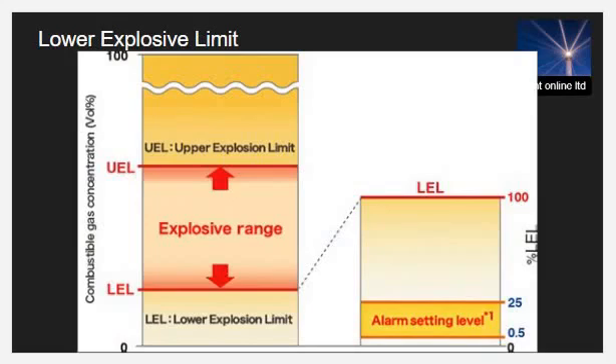Being above the upper limit is not particularly safe either. If a confined space is above the upper flammable limit and is then ventilated or opened to an air source, the vapor will be diluted and the concentration can drop into the flammable limit range.